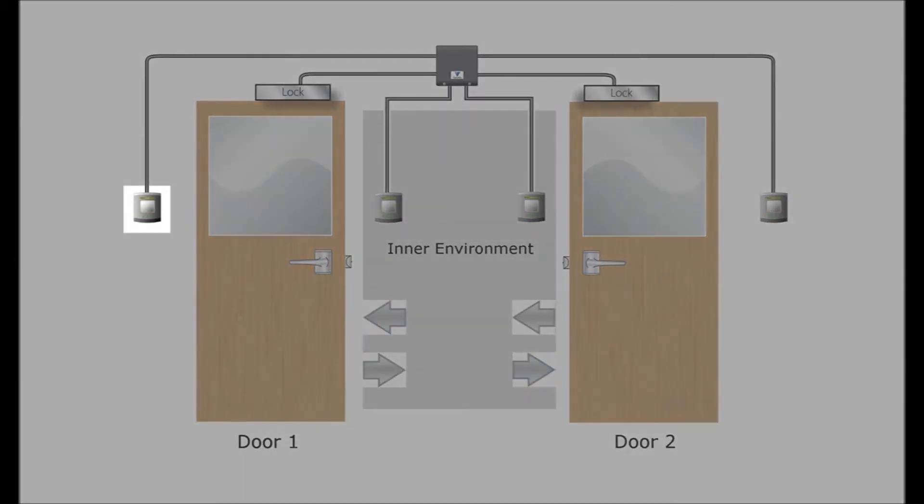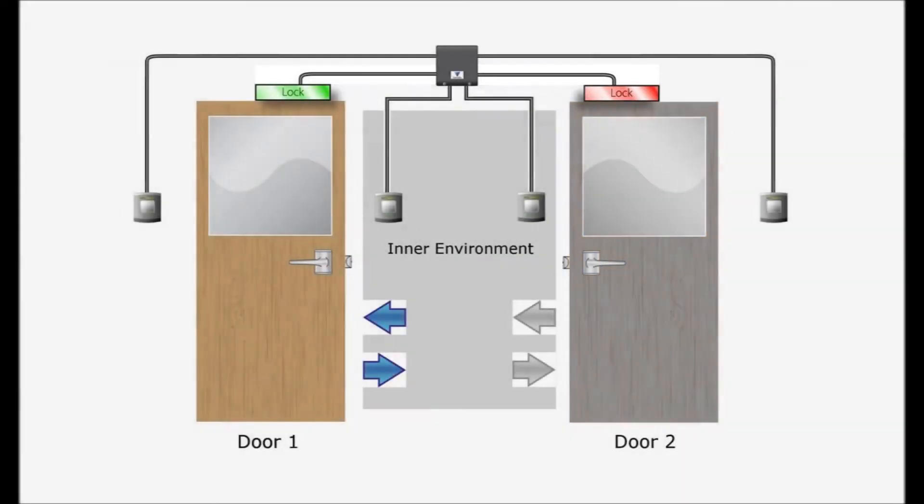The system follows the sequence: first of all, to request to open a door, the switch on the contact for door one is closed. The system reads the status of door two and understands that it is in the closed position, and that will accept the door request and energize the lock-out relay. Door one is now accessible.